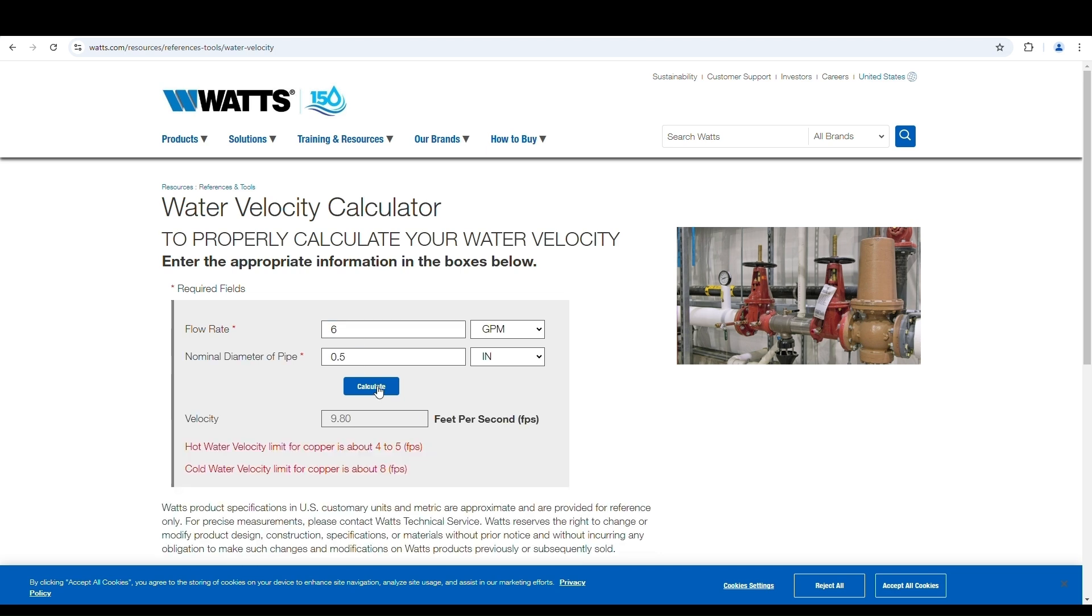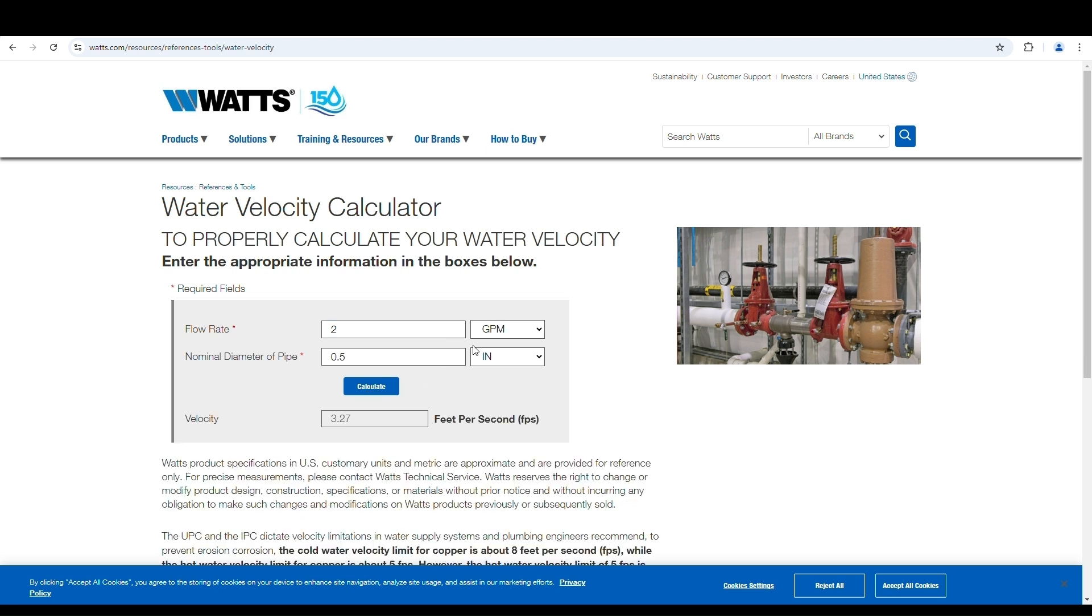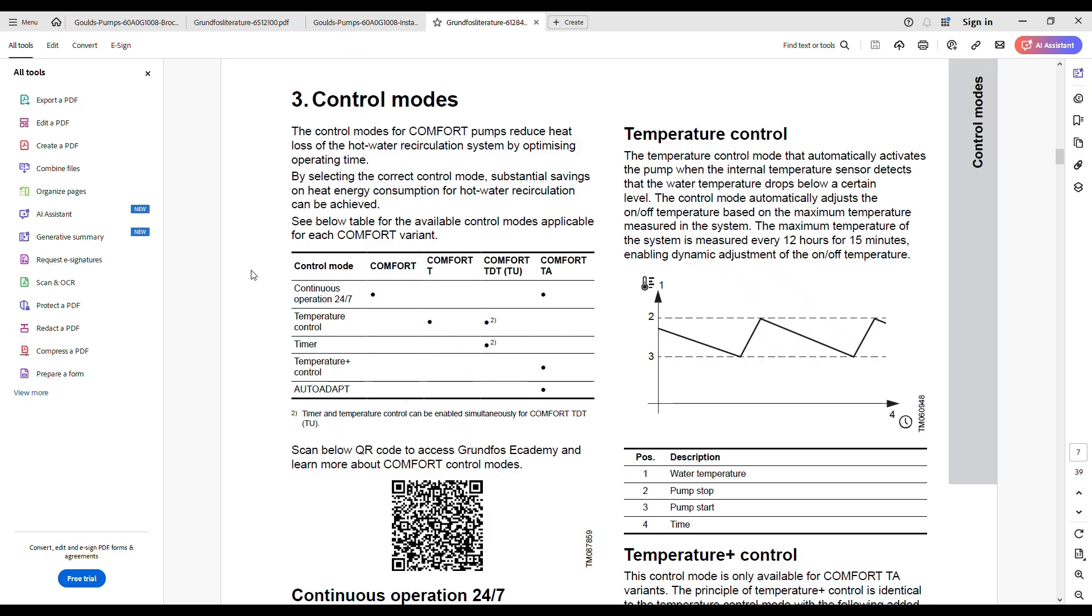I liked that one because it was below 4. The recommendation is 4 to 5 feet per second, if you remember. See here, 4 to 5. So I decided I wanted to limit my pump to have a maximum of 2 GPM. It means that maybe the loop when it's cycling the water might not heat up quite so fast, but I 100% wanted to avoid any chance of eroding away any of my copper pipe or fittings.